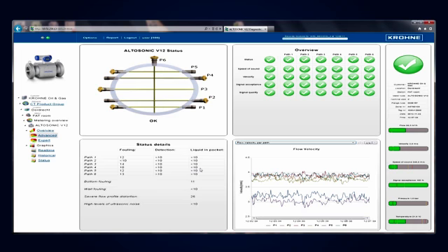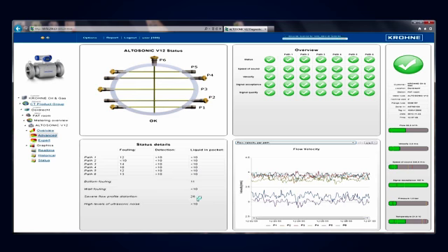If values are higher than 66, we give a real alarm. This means strong contamination, more than 2 paths failed, the meter is outside of custody transfer accuracy, and immediate action is required. One thing you see here, that the flow profile distortion is quite high, it's at 26. It's just below 33. There is no reason for warning.